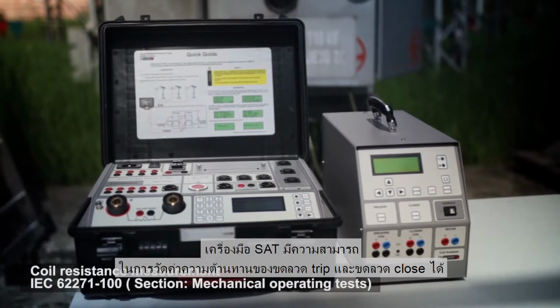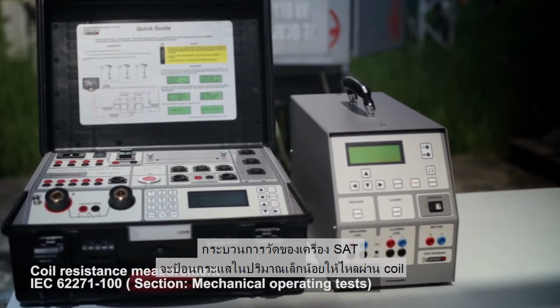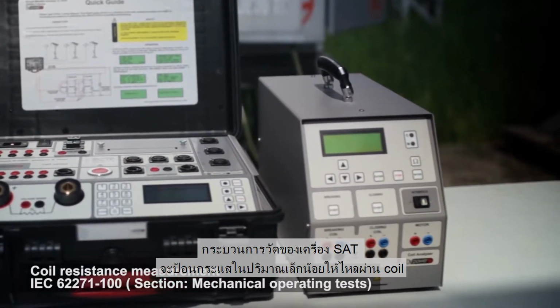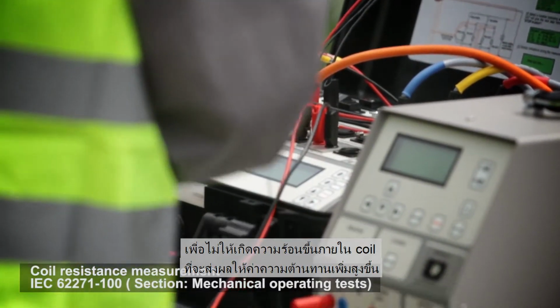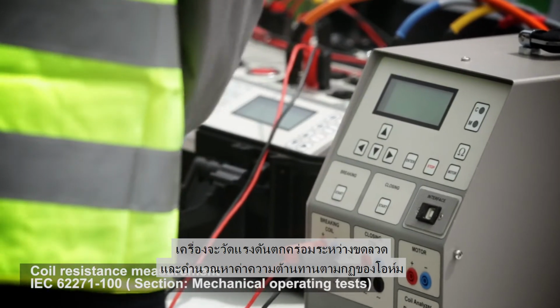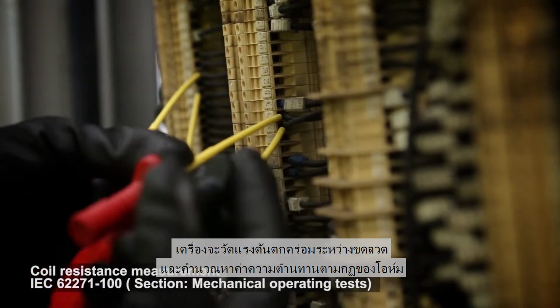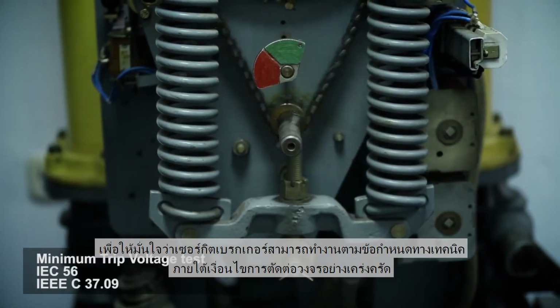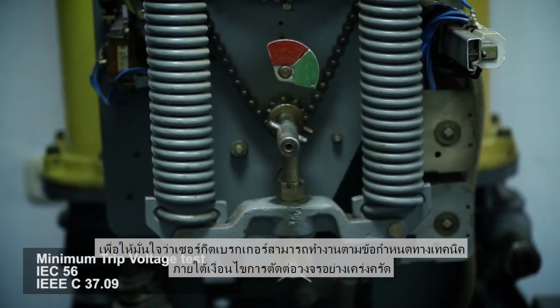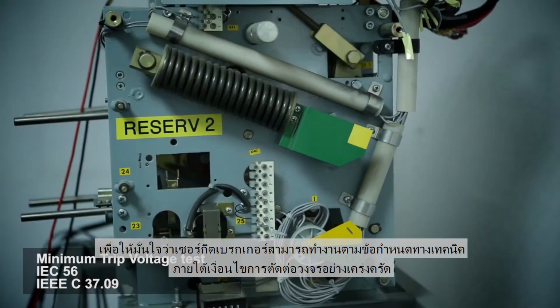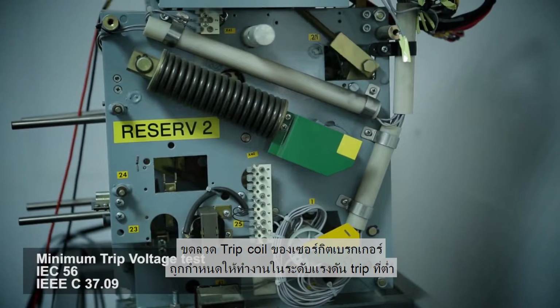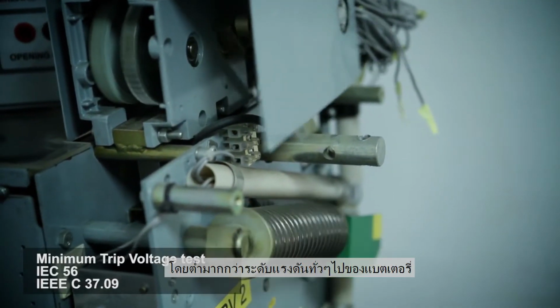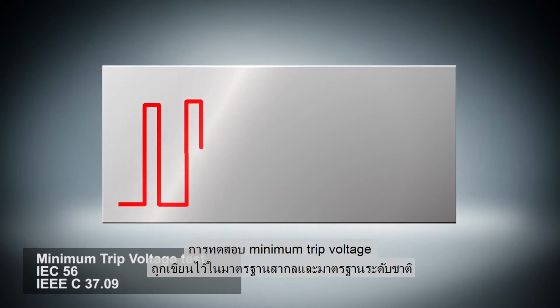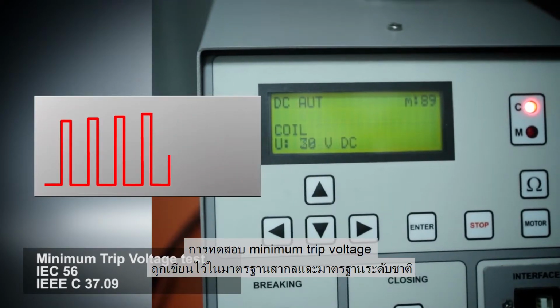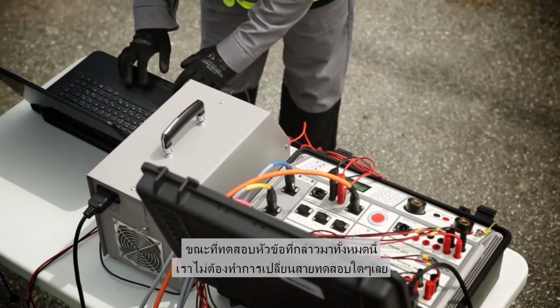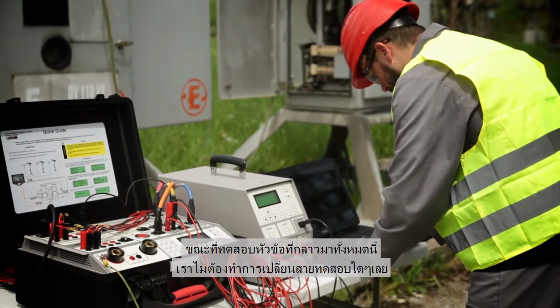The SAT instrument can measure the trip and close coil resistances. Its measurement procedure generates a very low current through the coil, which would not heat up the coil and consequently increase its resistance. The corresponding voltage drop is measured across the coil and used to calculate resistance according to Ohm's law. To ensure that a circuit breaker operation is within specification under the most rigorous conditions placed on its tripping ability, the circuit breaker trip coils are specified to work with a minimum tripping voltage much below the nominal battery voltage. The minimum trip voltage test is described in a number of international and national standards. All these tests are performed without changing the lead connections during the test.